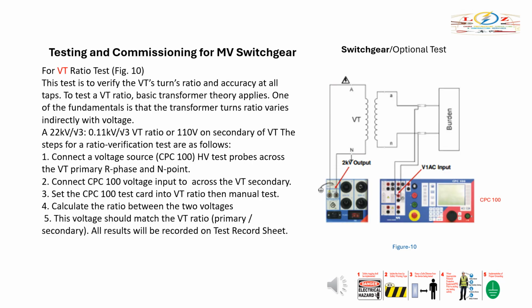For VT ratio test, as shown in Figure 10, this test is to verify the VT's turns ratio and accuracy at all taps. To test a VT ratio, basic transformer theory applies. One of the fundamentals is that the transformer turns ratio varies indirectly with voltage. At 22 kV over square root 3, 0.11 kV over square root 3, VT ratio, or 110 volts on secondary of VT.